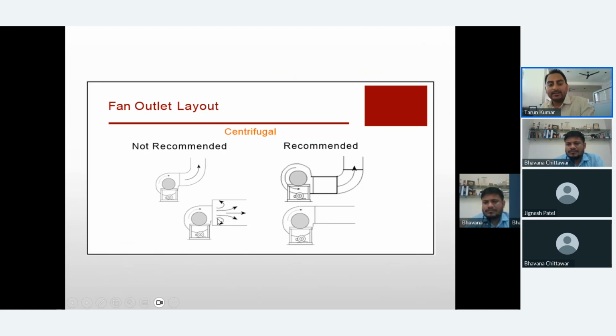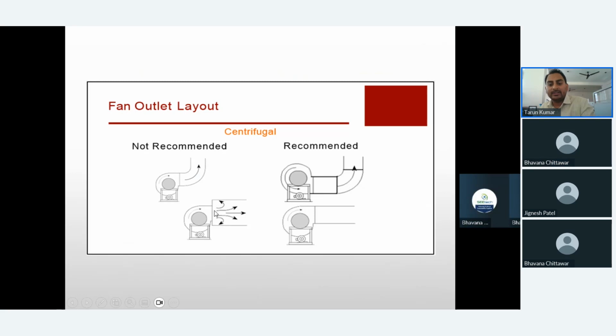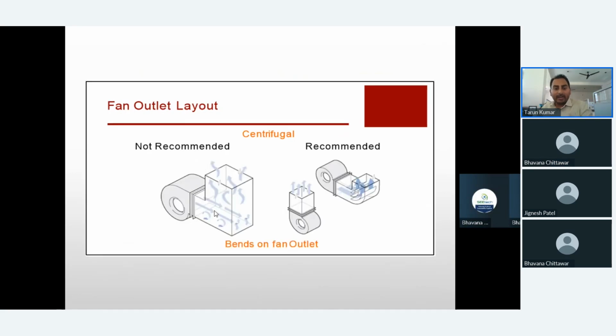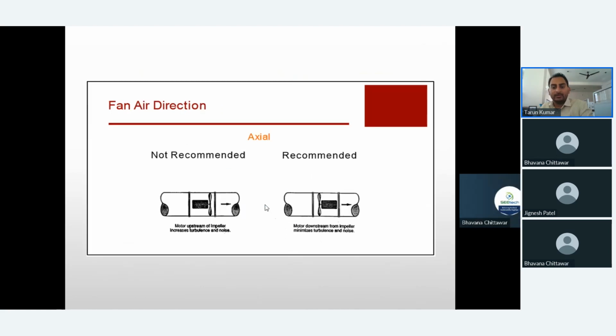At the same time, when you are putting in the duct, try to avoid oversized ducting. Try to use the same size of ducting, because otherwise you can see air turbulence is there, some of the air is going back, and it will again create back pressure in the system. Further, with such an arrangement, rather than going for a 90-degree fan, you can go directly with the top discharge fan, and at least two bends are avoided immediately. So the right orientation in fan selection is also very important when you are making the installation.